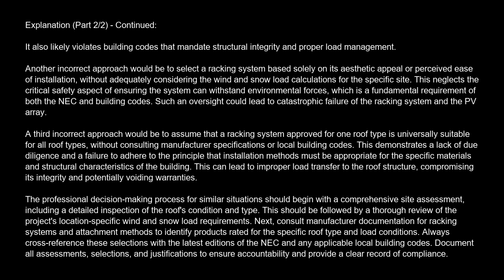Another incorrect approach would be to select a racking system based solely on its aesthetic appeal or perceived ease of installation, without adequately considering the wind and snow load calculations for the specific site. This neglects the critical safety aspect of ensuring the system can withstand environmental forces, which is a fundamental requirement of both the NEC and building codes. Such an oversight could lead to catastrophic failure of the racking system and the PV array.